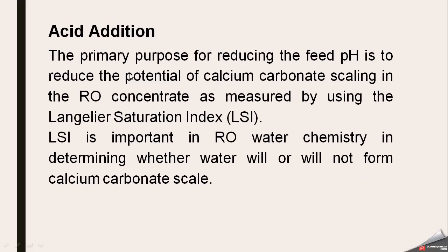So, acid addition. The primary purpose of reducing the feed pH is to reduce the potential of calcium carbonate scaling in the reverse osmosis concentrate, which can be measured using another important index known as the Langelier Saturation Index, or famously known as LSI.